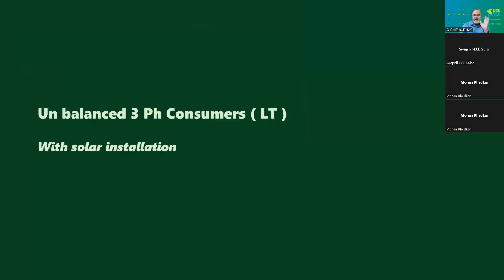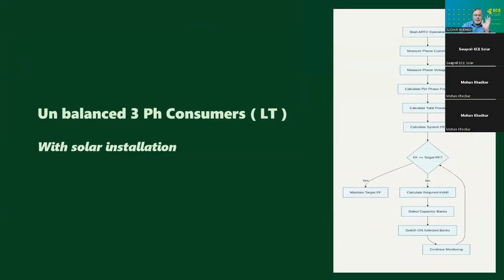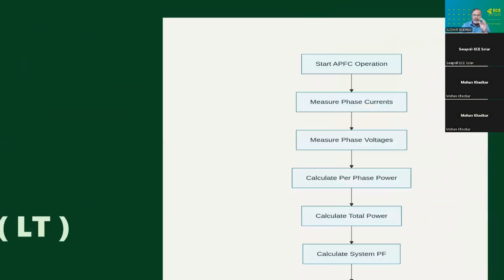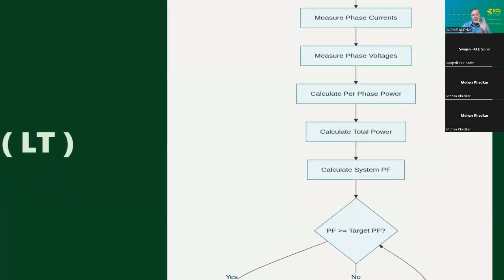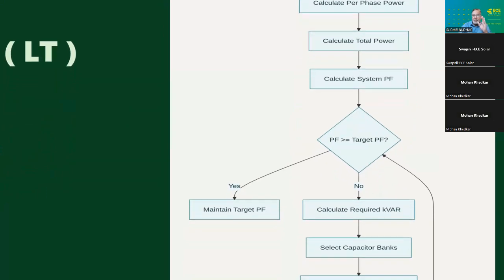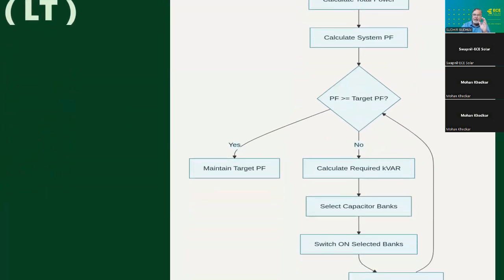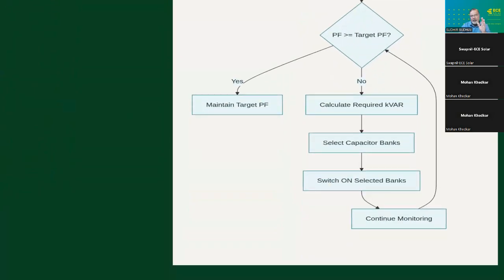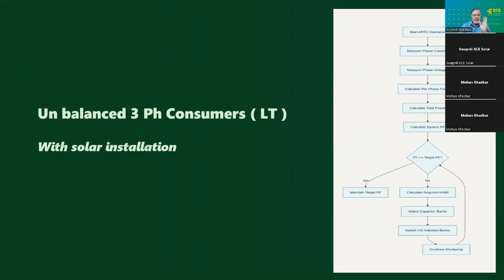Now, talking about a solar installation, we'll have to look at the logic of how the APFC relay works. It starts the operation, measures phase current, measures voltages, calculates phase power, calculates total power, calculates the requirement of power factor, and accordingly checks whether power factor is within the range or not. If not, then it calculates the required kVAR, selects the capacitor bank, switches on the selected banks, and continues. This process continues till the steady state is achieved. If yes, then it maintains the power factor. That's how the logic in any APFC relay works.